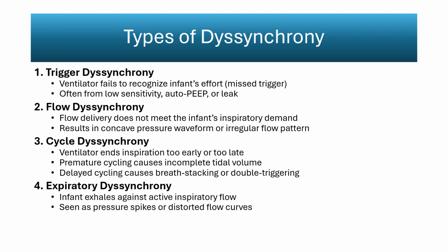Flow dyssynchrony develops when the flow delivered by the ventilator does not match the infant's inspiratory demand. If the ventilator provides less flow than the child is trying to pull in, the infant must generate additional effort, and the waveform begins to show a concave or scooped appearance. Flow dyssynchrony can also create irregularities on the flow time curve as the ventilator and infant alternately compete for control of inhalation.